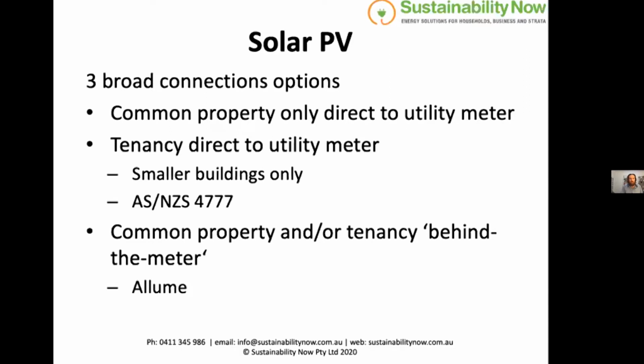There's also Australian Standard 4777, which can be problematic. It says that if you have more than 30 kilowatts of solar installed on your building running through the same connection point, you essentially need a master protection relay, and then also a sub relay on each individual point of connection. For example, if you had a building with 30 apartments and 1 common property connection, and the total array size was over 30 kilowatts, you'd need a protection relay at the main entry to the connection point of the building, and then a sub relay on each of the 31 other connection points.